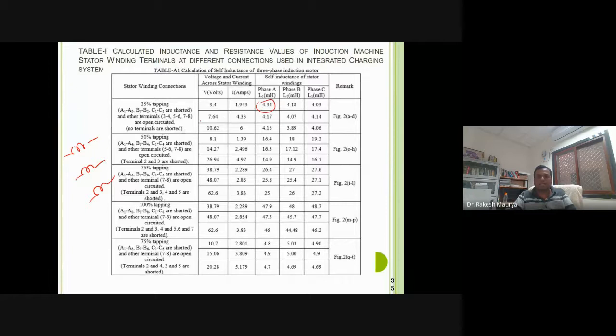We found that the self-inductance at 25% tapping is 4 millihenry, 4.1 millihenry, 4 millihenry for phase A, phase B, and phase C. Similarly, at 50% tapping, it is 16, 18, and 19 millihenry. Again for 75%, it is 26, 27, and 27 millihenry. So what I want to conclude is we have a variety of inductance ranging from 4 millihenry to 40 or 50 millihenry achievable through different combinations of this connection.